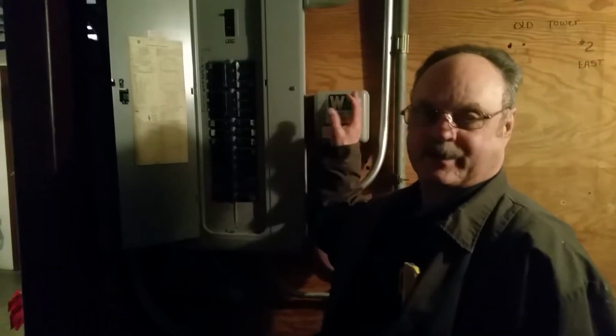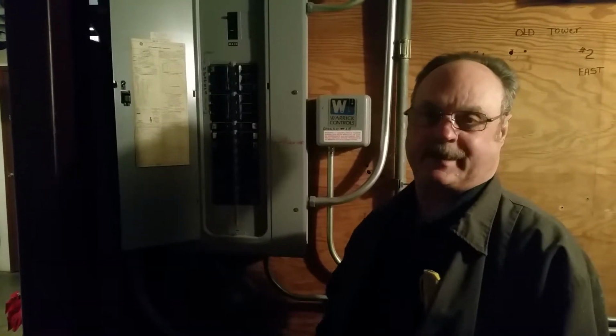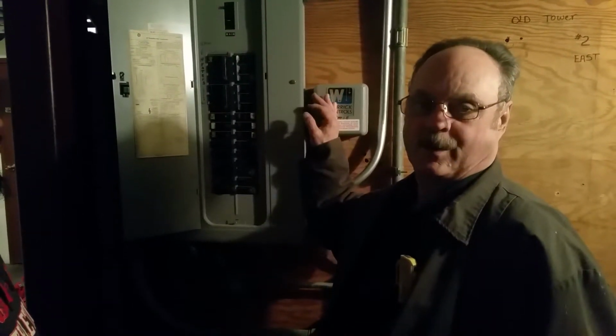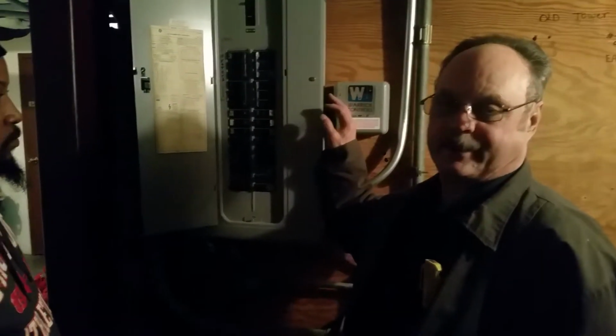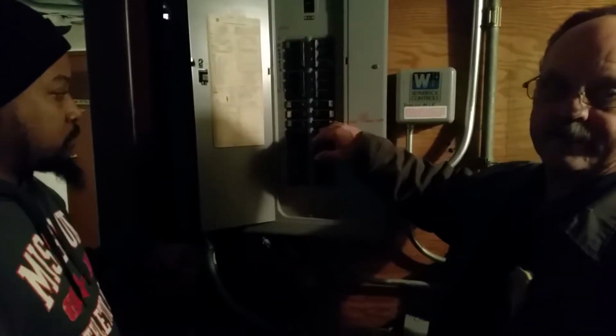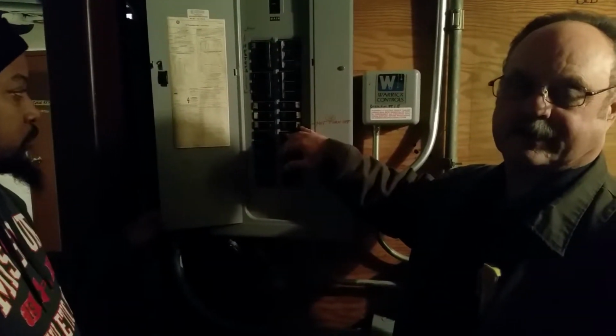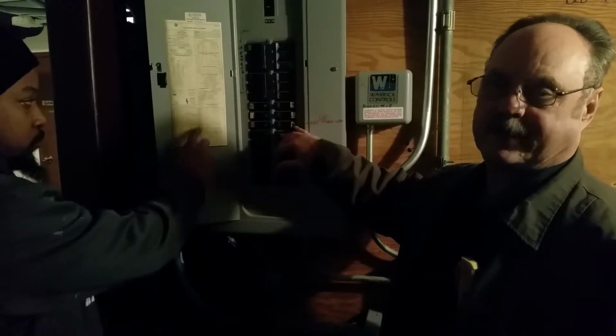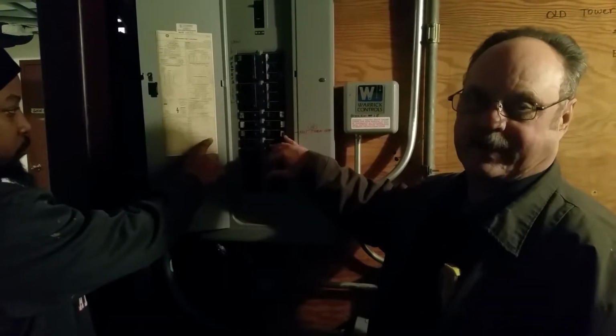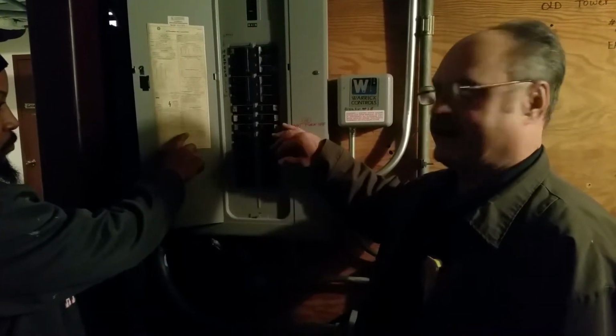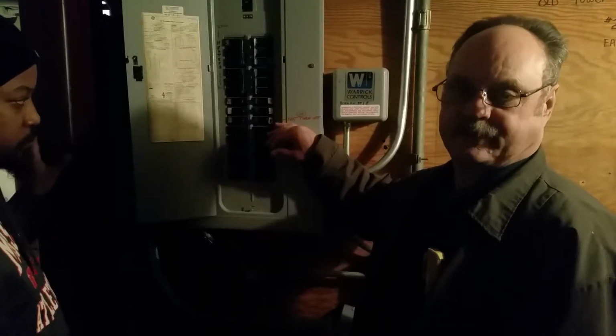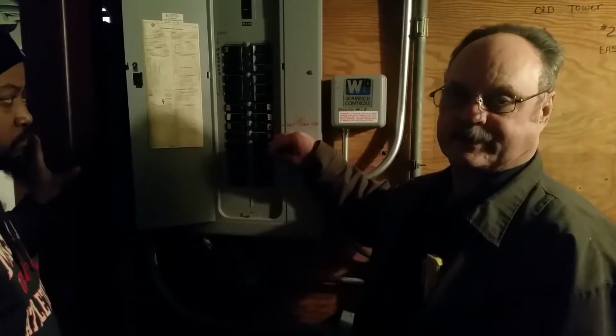What we're doing here today, we're going to drain the cooling tower today, and the first step that I do, I shut the automatic fill off the cooling tower. So I shut breaker number 18 off to kill the power to the water controlling device, including the solenoid, which is located down in the basement. This breaker is on the 6th floor abandoned elevator shaft.